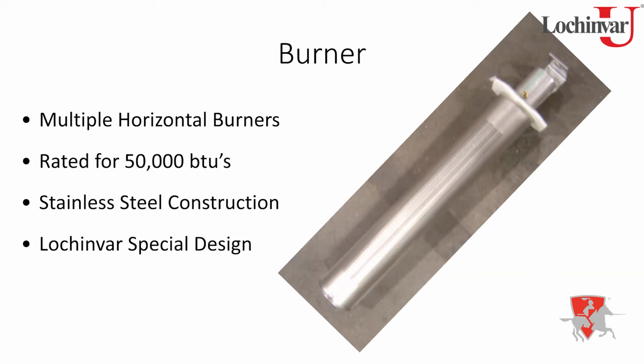If that baffle wasn't there for some reason, what you would end up with would be a very tall flame at the front of the burner and then a very short flame at the back, because the gas air mixture wants to go the path of least resistance. Just like water. Yeah, just like water. So it's going to go through those first openings. So you end up with that huge flame at the top, very short flame at the back, and then you're going to end up overheating the burner, burning the burner up. And that Venturi tube is, like Charles said, flipped 180 degrees from the top burner ports that you're looking at right now in this picture.